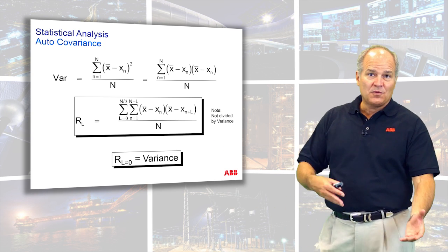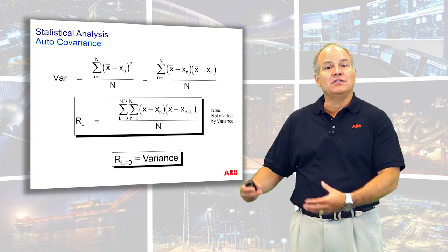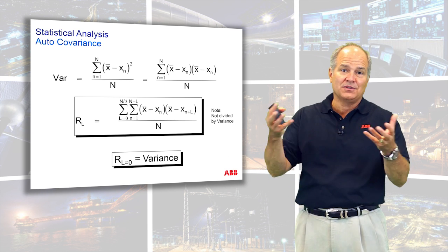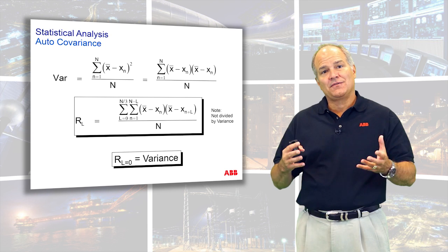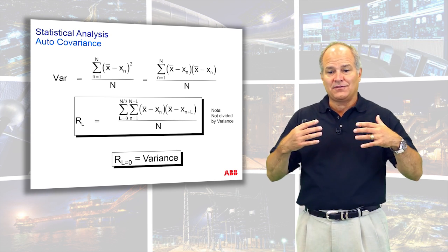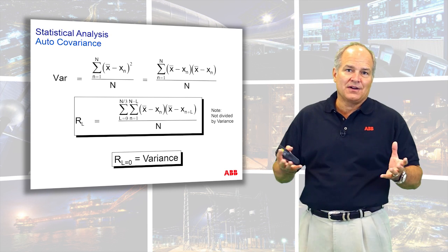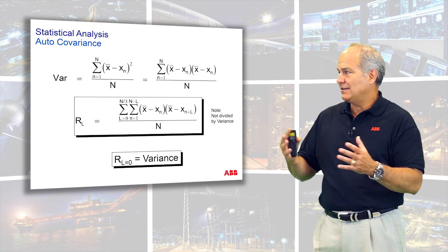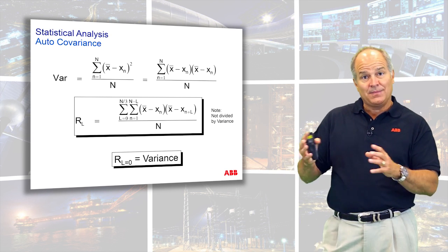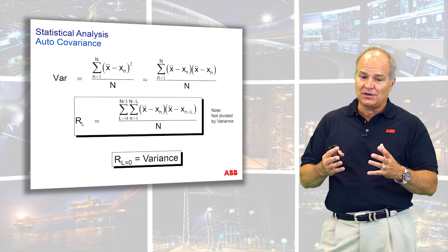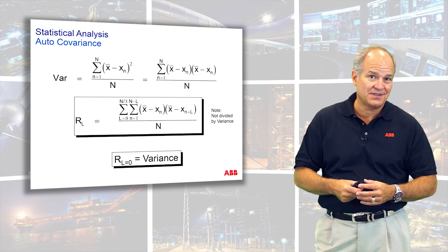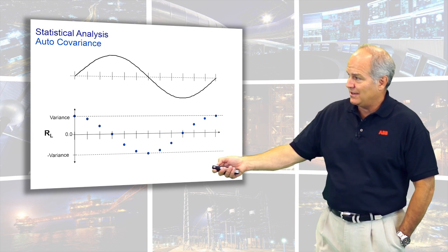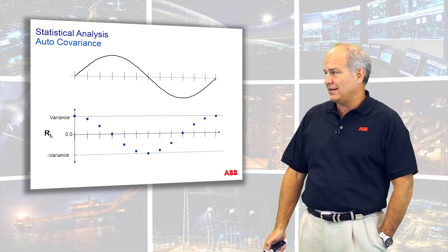Sometimes if I'm doing a before and after control evaluation, I'll use covariance because you can see the energy in the signal stops, and it's a real neat comparison. That's where if you use autocorrelation before and after, it can amplify the very thing that makes what you did look different. So I like to sometimes use covariance when I'm doing comparisons before and after. I like correlation when I'm trying to normalize and look at a bunch of things at once. Now this is showing in variance terms. You can see it starts. So they look exactly the same.